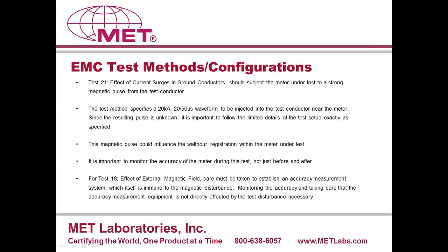It has a very high magnitude of 20,000 amperes or 20 kiloamperes with a rise time of 20 microseconds and a half-life of 50 microseconds. Now this impulse shape is quite similar to a conventional surge impulse that is described under 61000-4-5, but the timing constraints are about 2.5 times longer. The strong magnetic impulse could severely impact the operation of a meter or even destroy it, which we see sometimes due to the very strong induction. The magnetic impulse inducer consists of a conductor that runs parallel at the back of the meter and is located very close to the meter, at a distance of 1.5 inches.